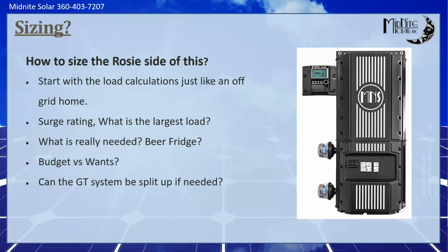Another question I get a lot is, how do I size the Rosie? How do I size my battery-based inverter for my AC coupled retrofit, if you will? A customer calls you and says, hey, I want to add battery storage. I want power when the grid goes down. Where do I start? Really, you have to look at it just like you would any other off-grid home. What do they want to run? What's their largest load they plan to start?